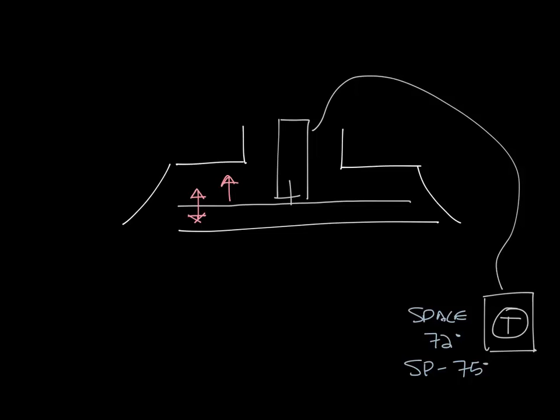So if you have a constant volume system that provides the same amount of airflow to all the diffusers at the same time, and let's say you have 10 diffusers total on this system, and this is one diffuser that starts to close, it might not be a big deal. The air will be split up amongst the other 9 diffusers.